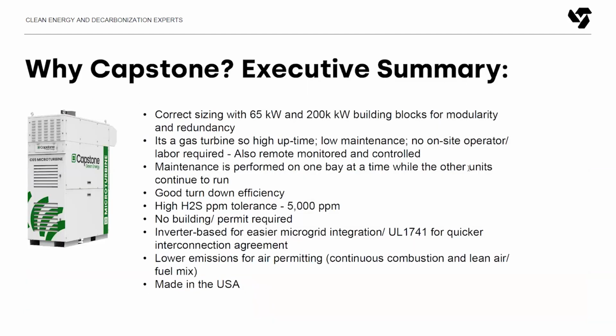Why use Capstone microturbines? Well, there's a lot of advantages, and I'll run through a few of them here today. But first and foremost, it's a modular system. We use smaller building blocks of a 65 kilowatt or a 200 kilowatt system to build larger power systems. And that gives inherent redundancy. It allows us to shut one unit off to do maintenance while the other units continue to operate, allowing for extremely high uptimes and extremely high total system efficiency.